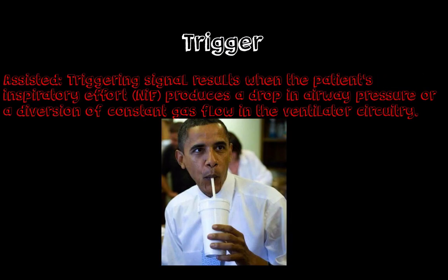The second type of trigger is an assisted trigger. An assisted trigger is a signal that results whenever a patient's inspiratory effort — which is negative inspiratory force — produces a drop in airway pressure or a diversion of constant gas flow in the ventilator circuitry. Here, as you see, the sucking motion is basically creating a negative inspiratory force. And whenever you do that, this will either drop the pressure in the circuit or divert flow in the circuit. Whenever flow or pressure is diverted in the circuit, the machine senses that and understands the patient is making an effort, so it delivers a breath. An assisted trigger is entirely governed by patient effort, done via a drop in flow or a drop in pressure in the circuit.